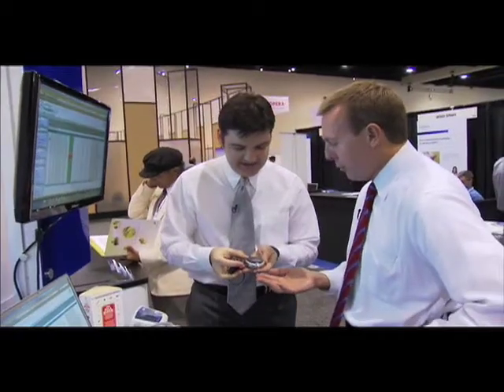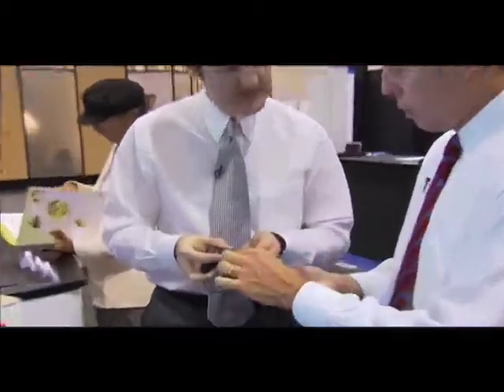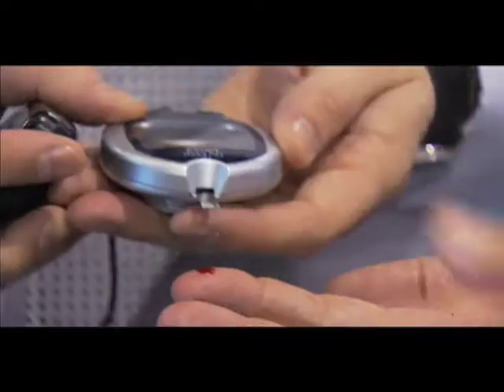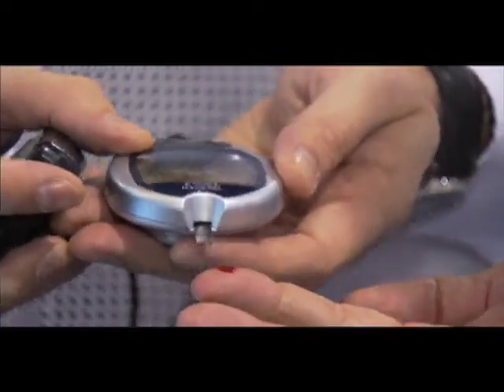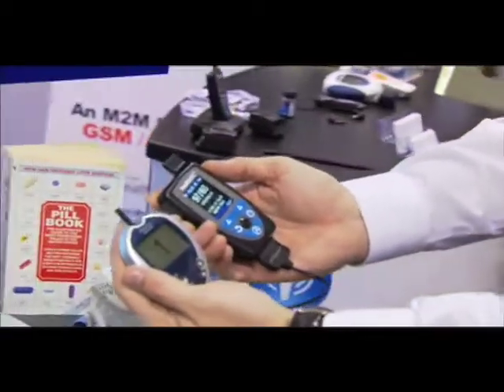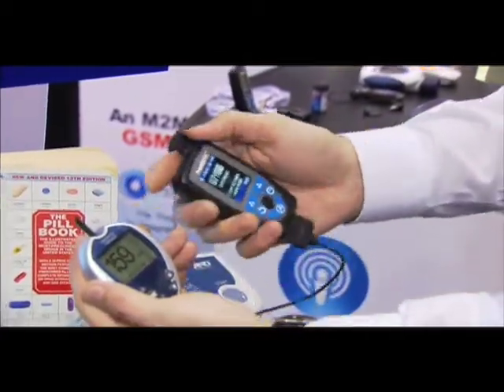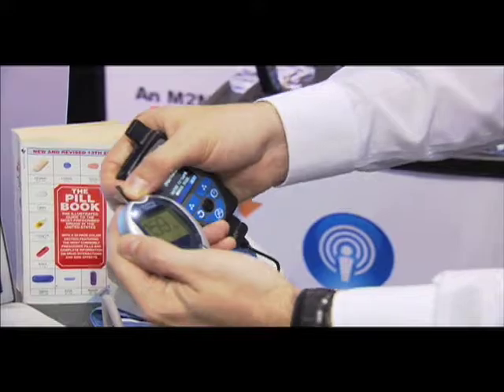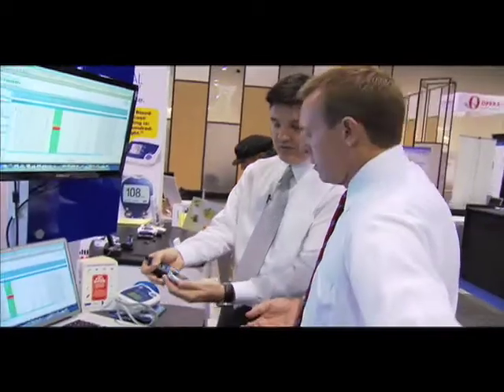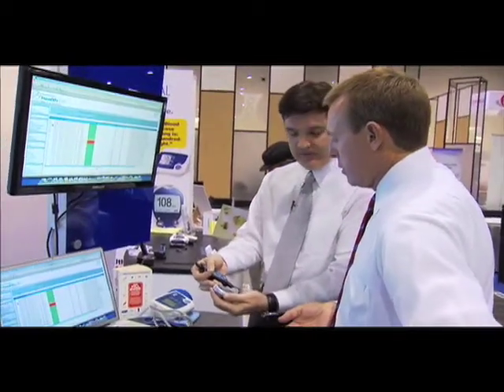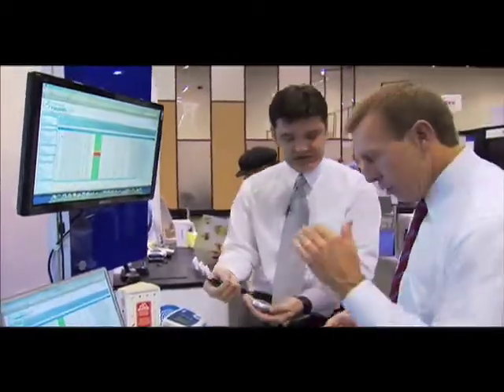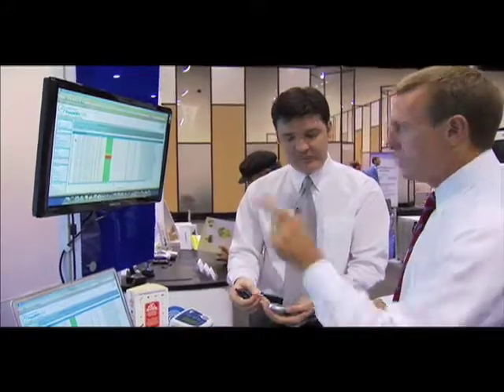Yeah. Now, so I've pricked my finger. Precisely. And now we're going to measure the blood sugar level. Absolutely. And this is exactly how a patient would do their test. So it counts down and it'll actually read that information. It's 159, and all they do is pull out the strip like they normally would, and that initiates the connection between our device and the glucose meter, and it will vocalize that reading back to the patient, and then be able to transfer that information. And transmit it once again over the cellular network into our database.